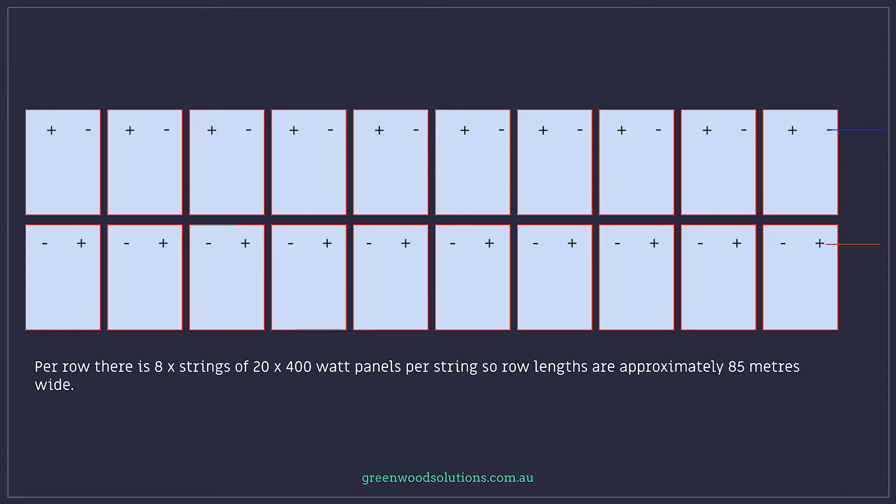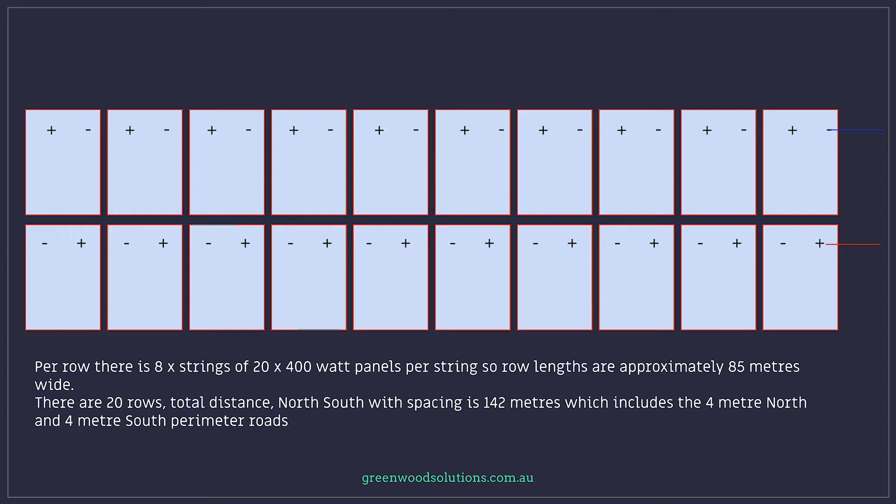Per row there's eight strings of 20 by 400 watt panels per string, so row lengths are approximately 85 meters wide. There are 20 rows, total distance north-south with spacing is 142 meters, which includes the four meter north and four meter south perimeter roads.